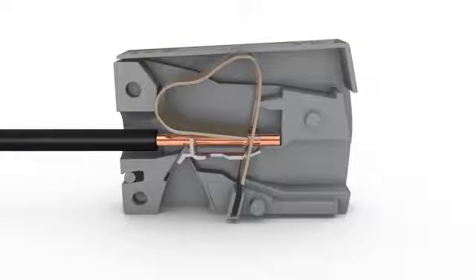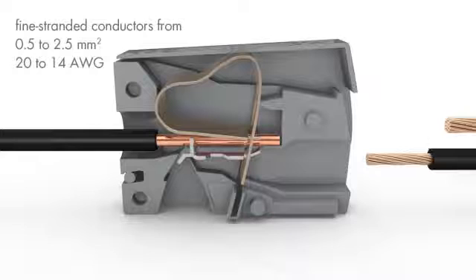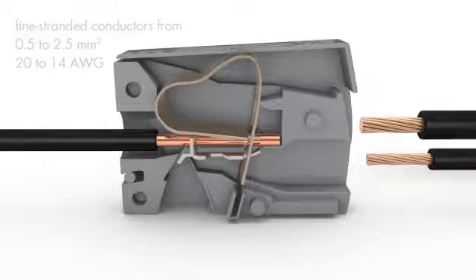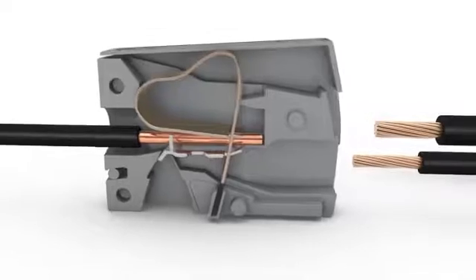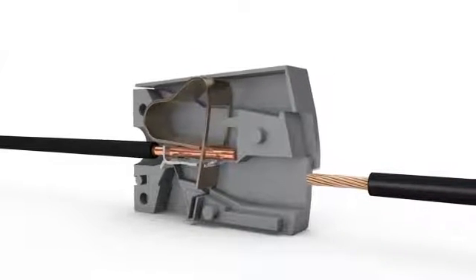On the lighting side, fine stranded conductors from 0.5 to 2.5 square millimeters or 20 to 14 AWG are terminated via cage clamp connection.